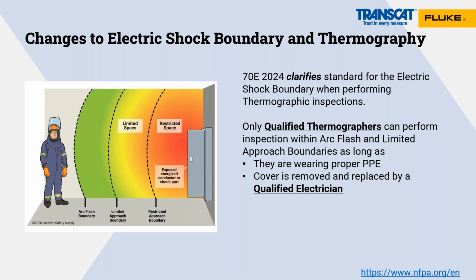But obviously, if I'm opening up an electrical panel and I'm a thermographer or somebody taking a thermal image, there's this arc flash boundary outside of which you would not have to have PPE gear on, but inside of that, or on the restricted area, you might have to have a full amount of arc flash clothing, insulated gloves, tools, and all those types of things.